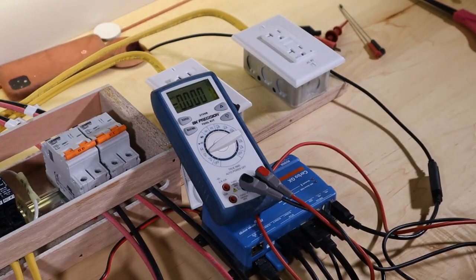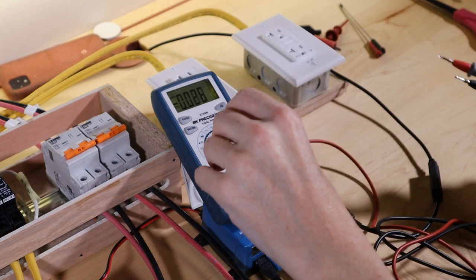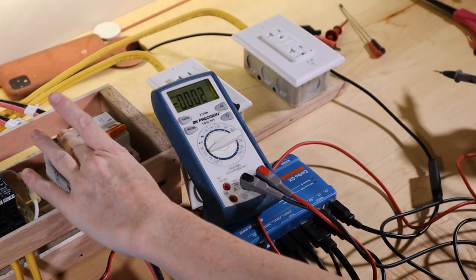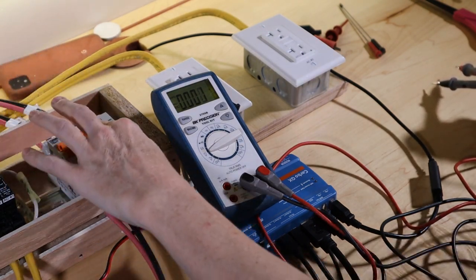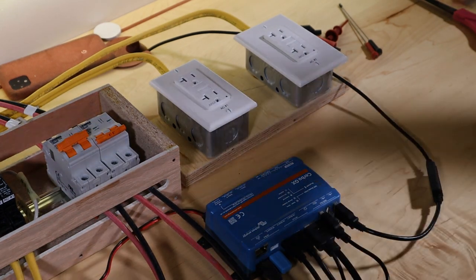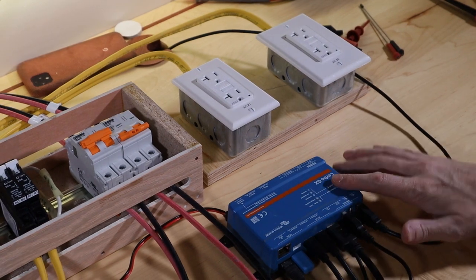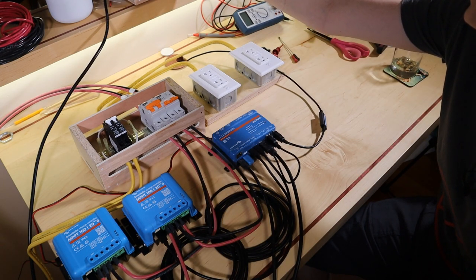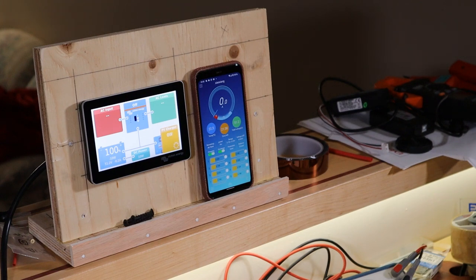Everything is off. Perfect. Now you can see the breaker. 0.15 volt, which makes sense because it's dark. Absolutely nothing on the other one. So this panel is definitely the one because it's picking up a tiny little bit of power from the moonlight. Turning it on, leaving this one off because it's not connected. Turning the battery back on. Pre-charge resistor. Battery on. All right, the CERBO's booting. Waiting for this to come up. PV chargers. It sees it. It sees the PV charger. There's zero watts coming in. In theory, tomorrow when the sun comes up, power should start coming into the battery.